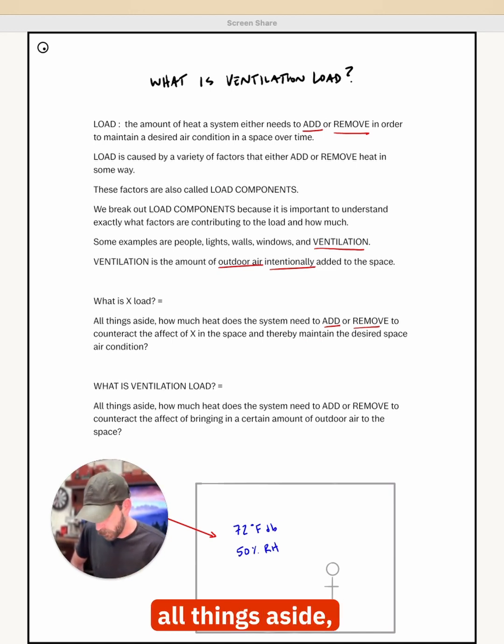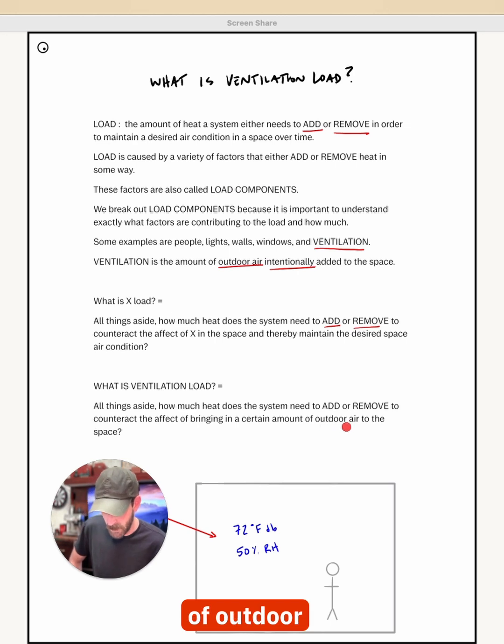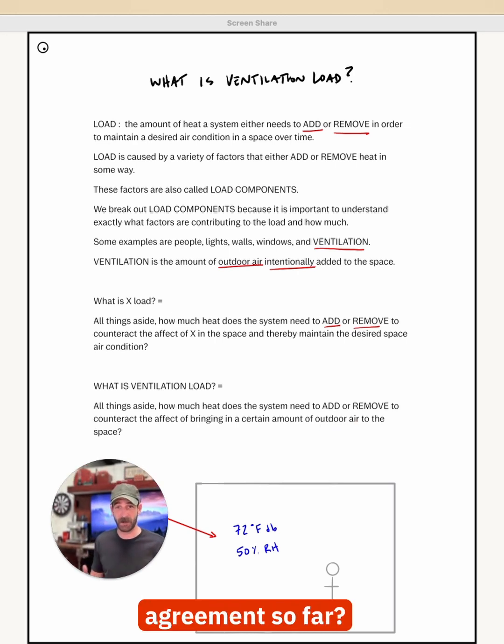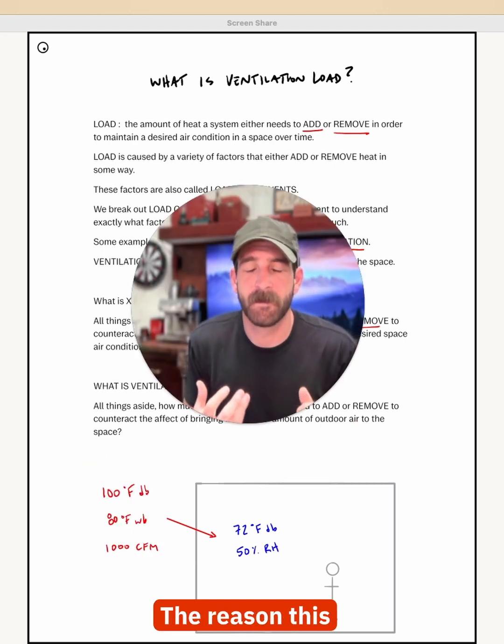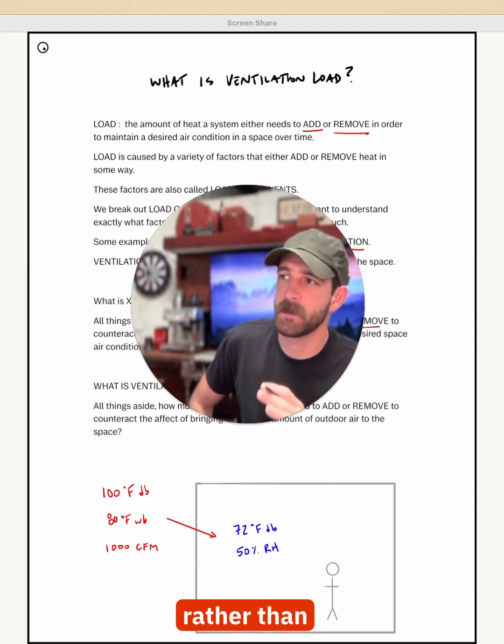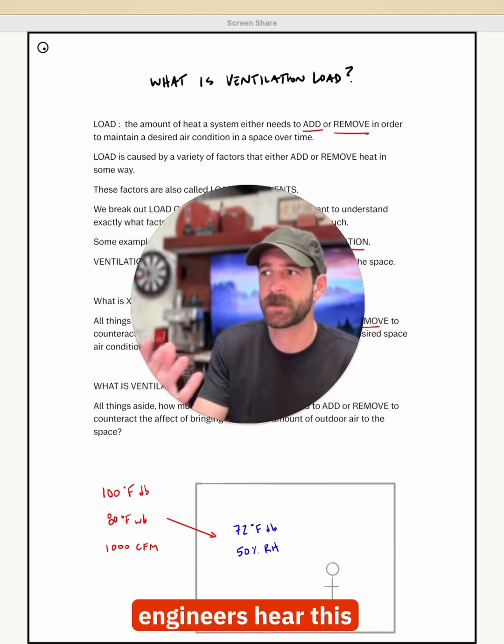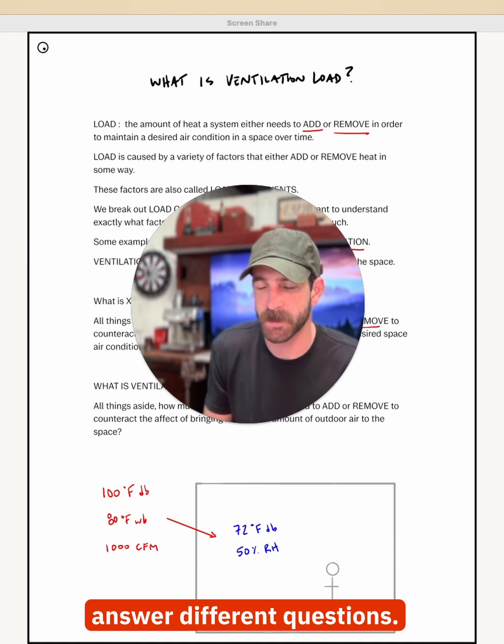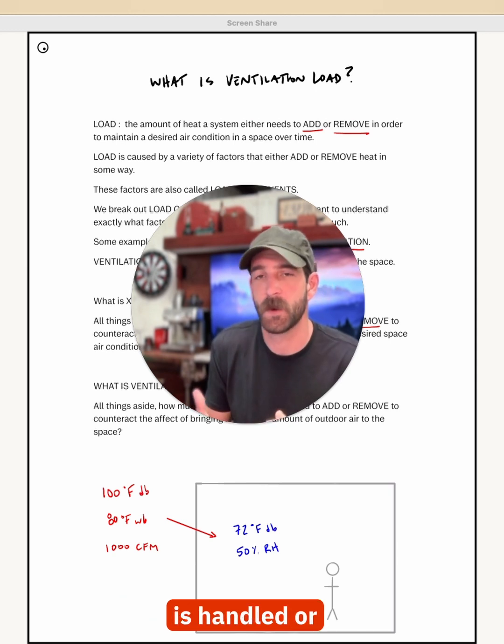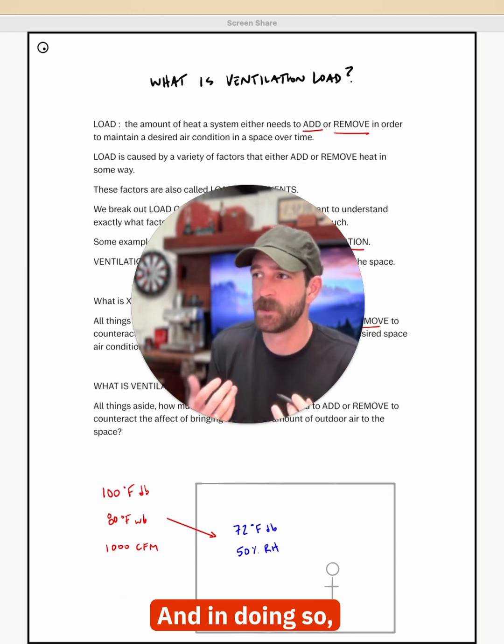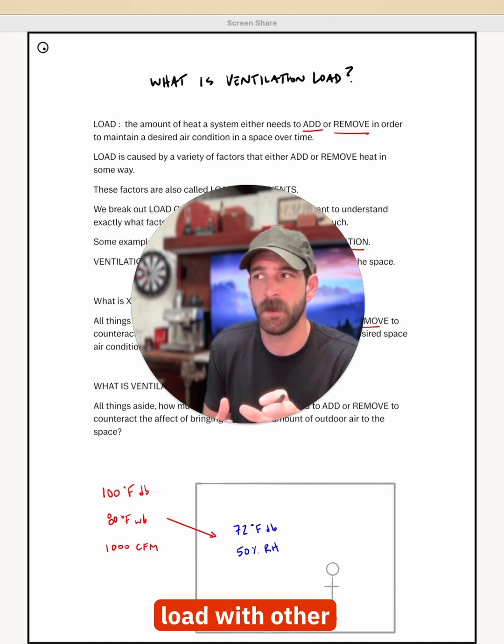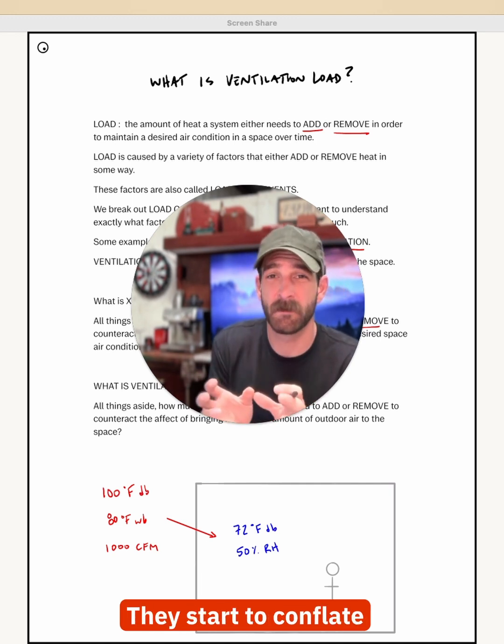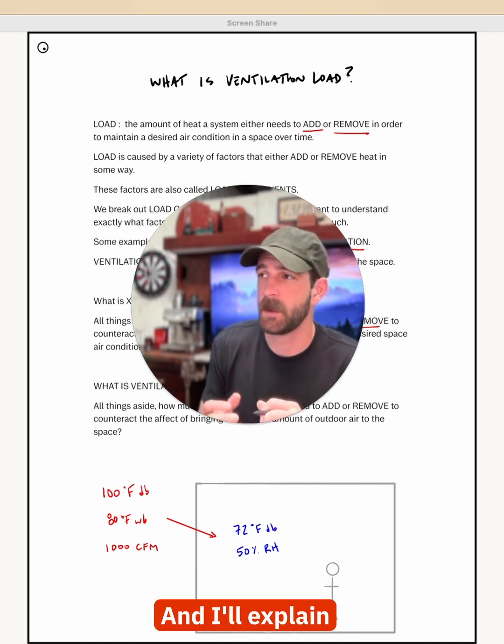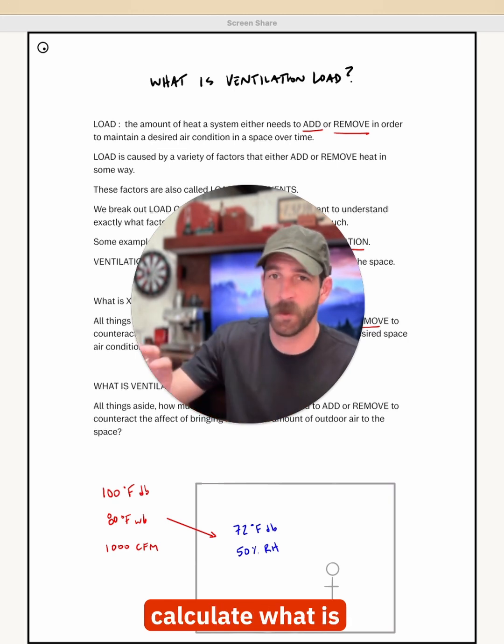We are asking, all things aside, how much heat does the system need to add or remove to counteract the effect of bringing in a certain amount of outdoor air to the space? Okay, in agreement so far? The reason this gets overcomplicated is because rather than answering the question literally, engineers hear this and they start to answer different questions. They answer how the ventilation load is handled or where it's handled. And in doing so, they start to conflate ventilation load with other load components. They start to conflate it with coil load, which is a different thing. And I'll explain this further, but first let's calculate what is ventilation load.